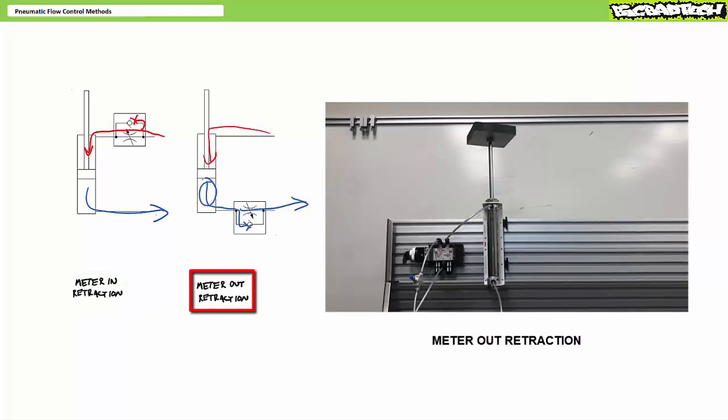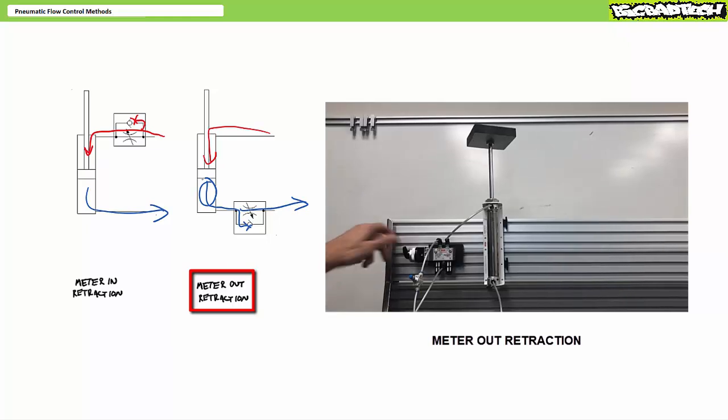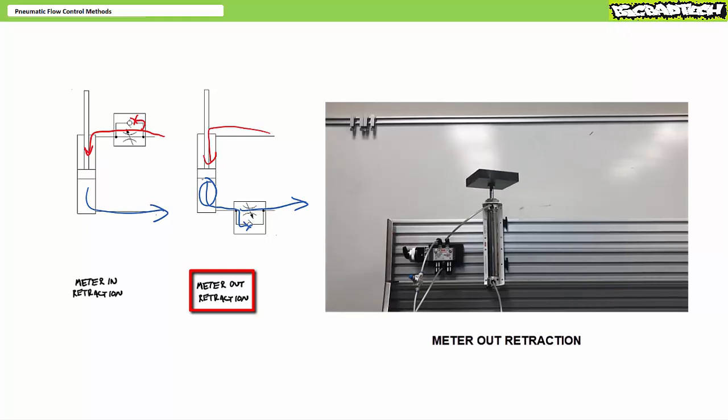In contrast, a meter out retraction configuration keeps a cushion of air trapped in the cylinder cap end supporting the lifted load during descent. The tighter the restriction, the slower the cap end drains and the slower the descent. When in doubt, meter out.